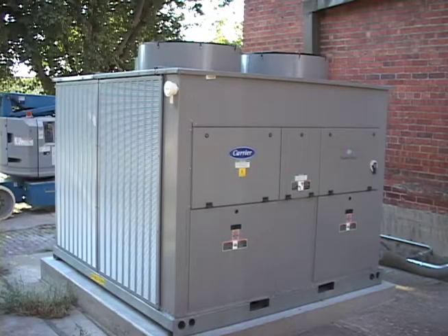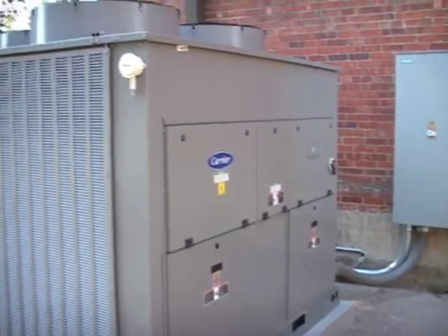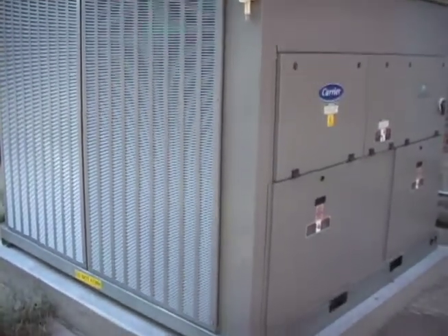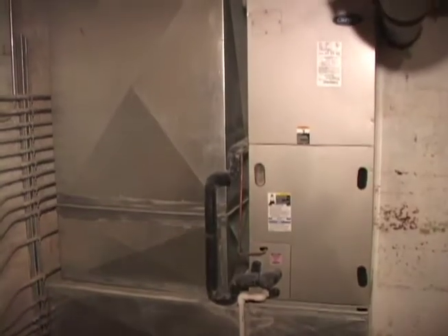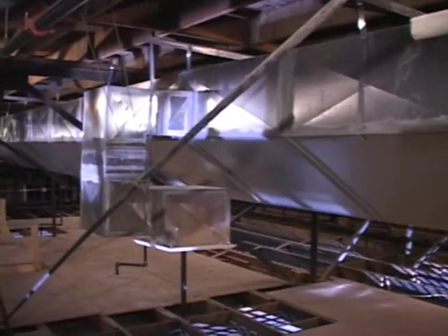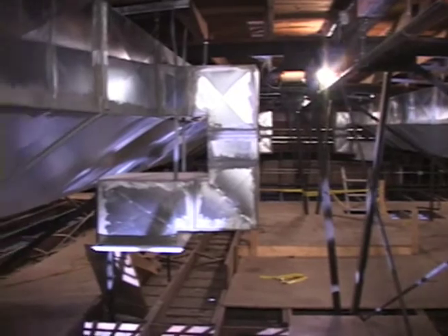The theater is now air-conditioned with 1 condensing unit and several smaller units and air handlers that allow for zone-controlled use. The theater condensing unit can run at as little as 5% of capacity and increases in steps of 5% for efficiency. A few of the air handlers are shown here. The smallest air handler is for the concession area only. The ductwork and mechanical installation by Waldorf Riley of Ark City is amazing to see in these attic shots.